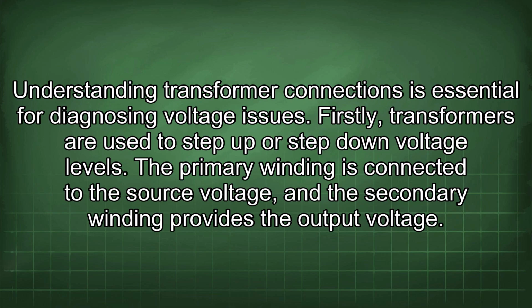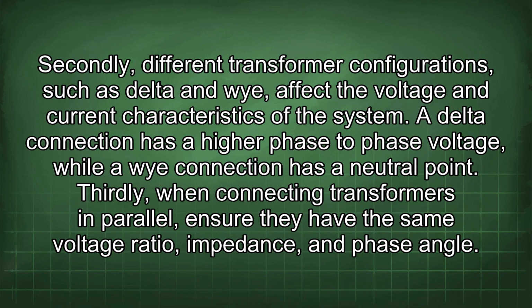Understanding transformer connections is essential for diagnosing voltage issues. Firstly, transformers are used to step up or step down voltage levels. The primary winding is connected to the source voltage, and the secondary winding provides the output voltage. Secondly, different transformer configurations, such as delta and Y, affect the voltage and current characteristics of the system. A delta connection has a higher phase-to-phase voltage, while a Y connection has a neutral point.